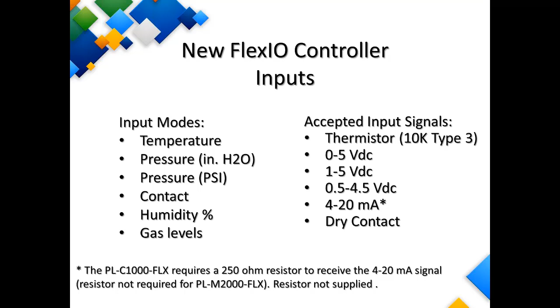All right. So for the outputs, what can drive our outputs? It can either be a local input, so essentially any of the inputs which you physically plug into the controller can be the source of the output. We can also control our outputs based on network variables as well. Some of these network variables can be occupancy, such as if we get it from our network controller. We can control our outputs based on our math functions. Our math functions are a feature in all our master controllers, like in the rooftop and in the heat pump controller, where essentially we can get a general zone demand from all our zones, just so we know if zones are calling for heat or calling for cooling. So we can use that to drive outputs.